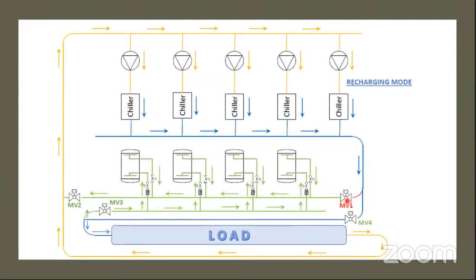So no, in this case, this valve remains closed. This is going to the load, and from here MV3 opens, and for the charging, the chill water goes here to charge the thermal storage tank simultaneously. The warm water returns here, and it mixes with the return water here and goes back to the suction of the primary pump. So that's our recharging mode. Once this is done, we are back to the normal mode.